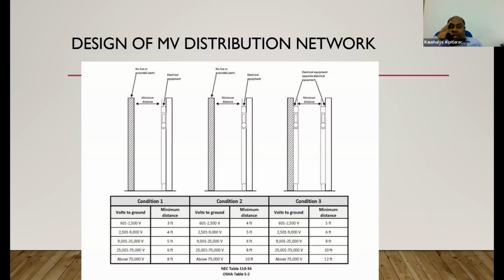Depending on the voltage levels, the distance is increased. If you take a 33 kV system, in the first condition, they say that's 6 feet. Earlier case, it was like 0.9 meters. Here, this is a little closer to 2 meters. If it is condition 2, that is 8 feet. That is more than 2 meters. In an application similar to condition 3, it is 10 feet, almost 3 meters.